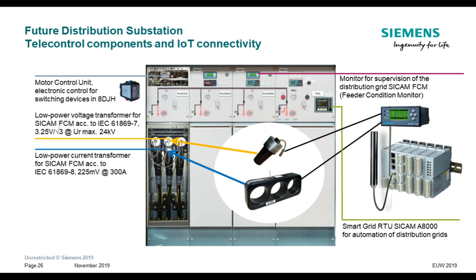The benefit is that it's really low voltage measurement, which comes with 3.25 volts, for example, for 24 kilovolts, or even 225 millivolts for 300 amps for the current sensor. These are really low power sensors, which do not create any data loss when disconnecting, and you don't need to bridge these connectors by removing, for example, the RTUs or the sensing equipment. That is something which needs to be installed in the field to get very detailed and precise voltages with high accuracy on the different feeders. But that is only the first pillar, the monitoring.